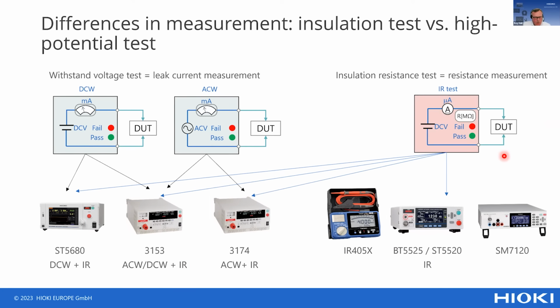Yeah. So ideally, the BT5525 is used on cell level. It can be used in pack level, but that's more for troubleshooting, basically. So if you have any issues with the pack and you want to determine which of the cells might be the problem, then you can disconnect this cell from the bus bar and do the individual check on the cell itself. But normally on a pack level, you will test with higher voltages, like for instance, 2 kV or 4 kV. Yeah. And for those customers and viewers being interested in withstanding test, but also insulation resistance test after cell production, so especially for pack and module, shortly we will also have a webinar for ST5680 talking explicitly about the next steps after the cell production.